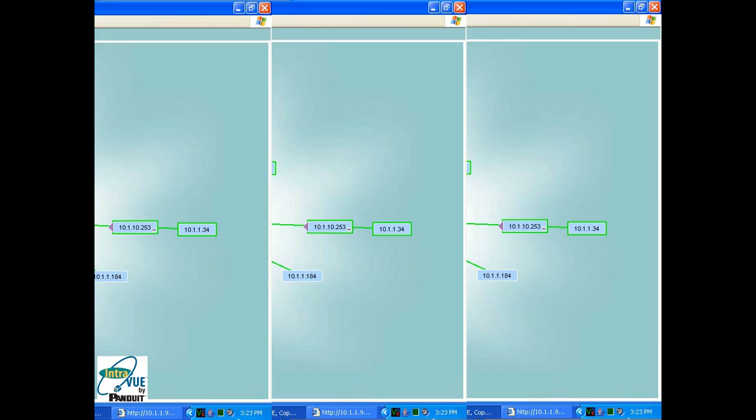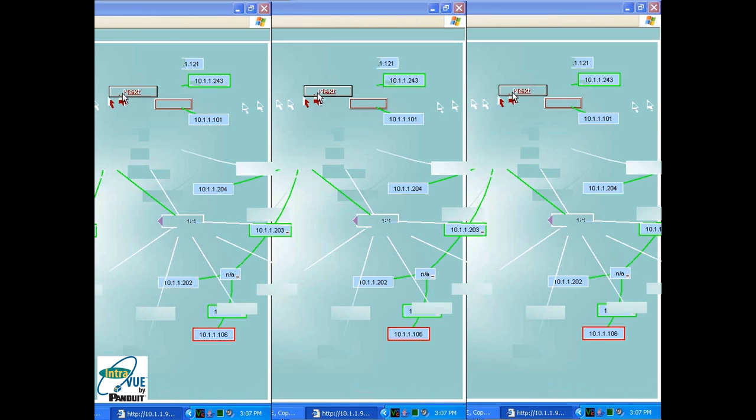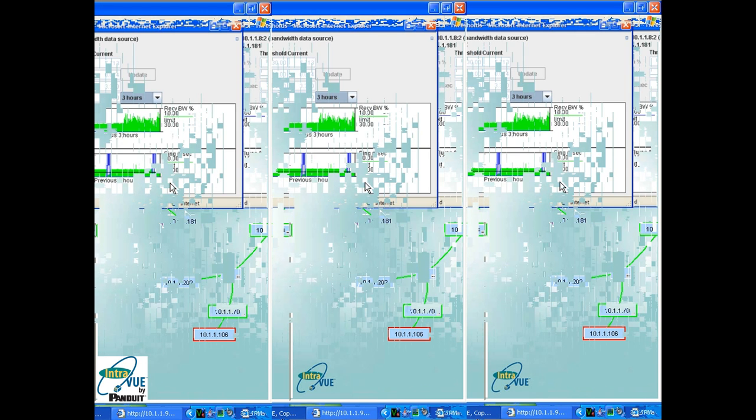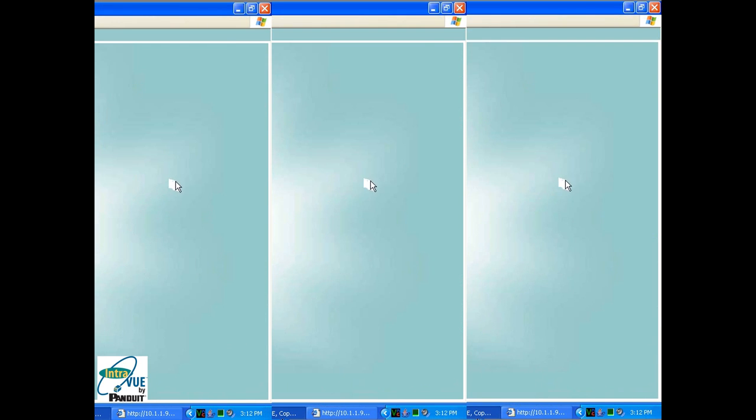Connectors or connection problems are frequent in plant floor applications, and IntraVUE is visually showing you that the connection between these devices should be investigated before it affects production. In this threshold dialog, we are revealing disconnects happening during a fixed time period and then recurring at a later time. This can identify a time-based problem, such as a motor starting, creating vibration or electrical interference. The errors can be caused by the device having periodic resets or issues due to other environmental problems.